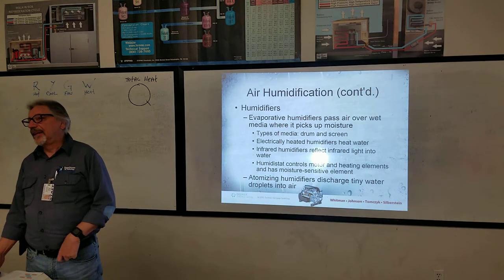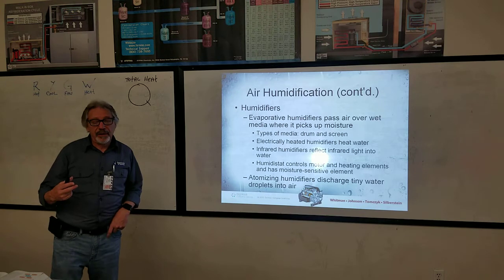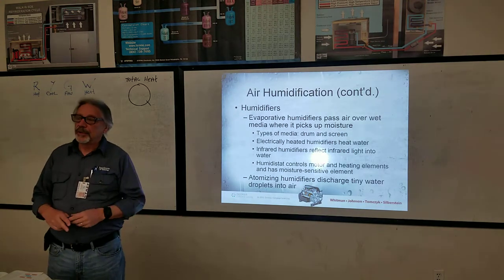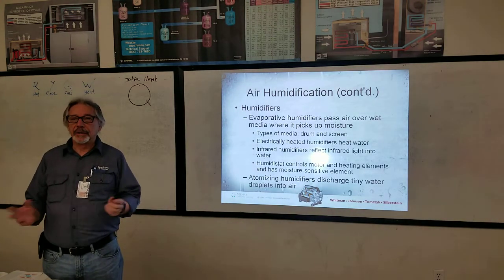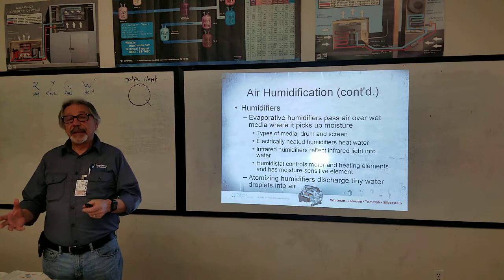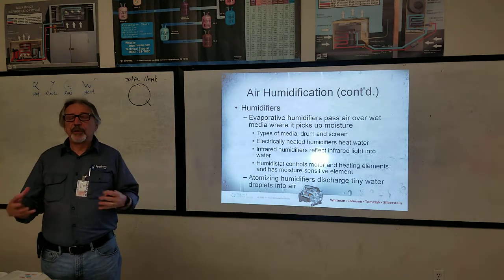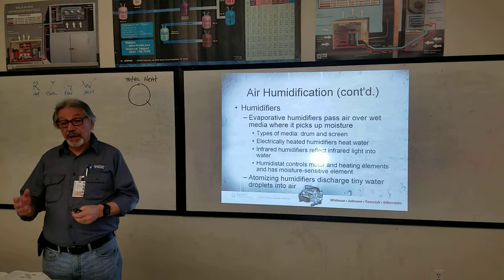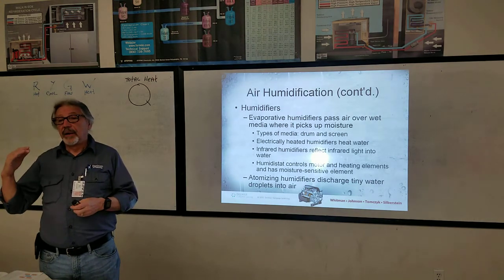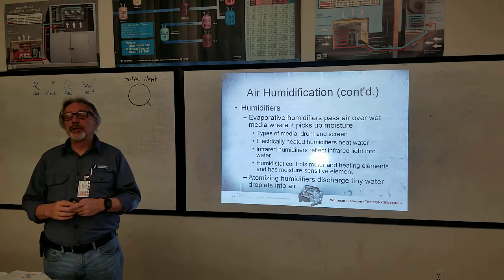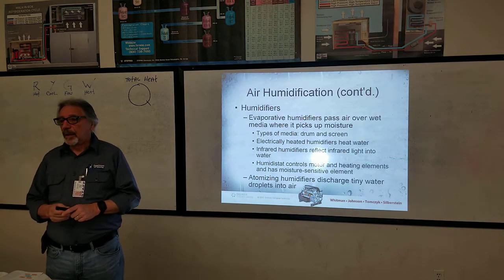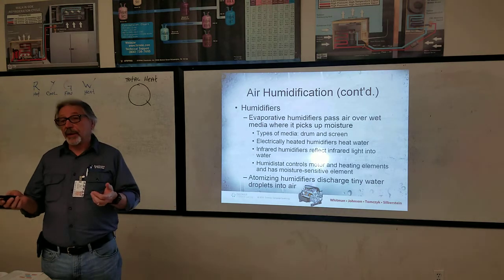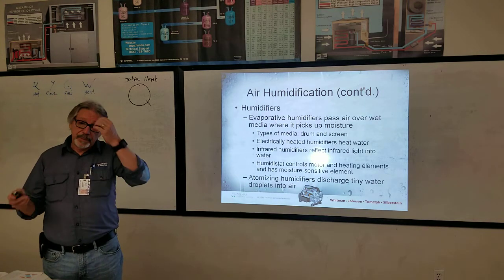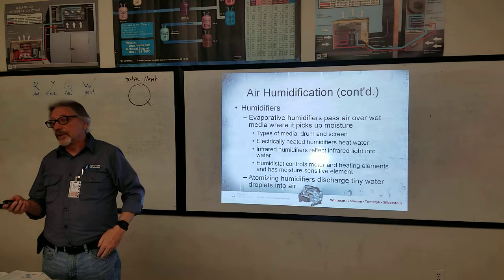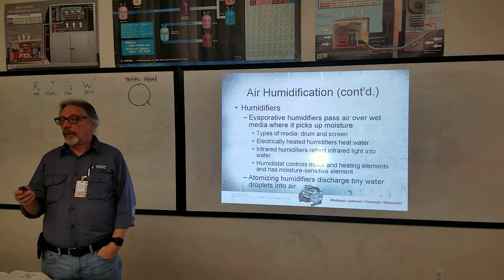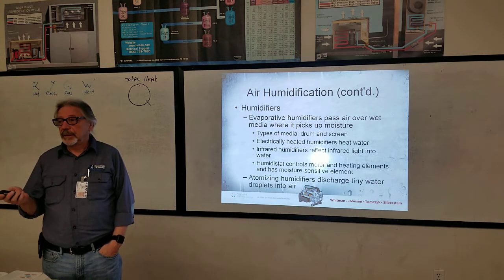All the heating of the air does is allow the air to absorb more moisture. That's all it does. So by heating the air, the air can absorb more moisture, so the relative humidity goes down, but the absolute humidity stays the same, because you still have the same amount of moisture in the air - it's just now vaporized as more of a percentage. Does that make sense?